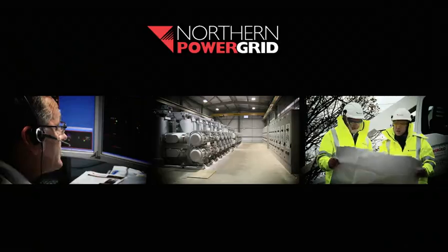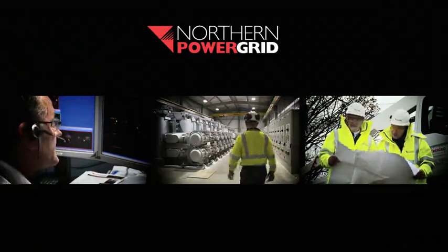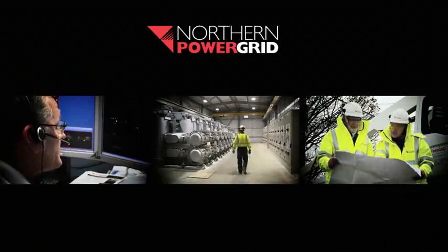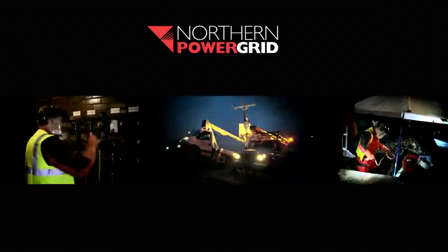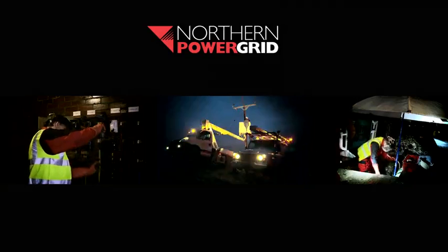We've covered HV switching, both on old and modern types of switchgear, low voltage distribution board operations, link box work on cutouts right from industrial service units down to the PL cutout, and live work on both overhead and underground mains. And in all cases we've covered operations, work and testing. And from all that data we were able to work out the fault levels at each particular piece of equipment, and then hence the incident energy levels.